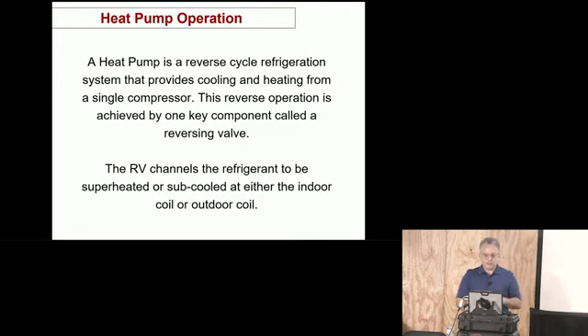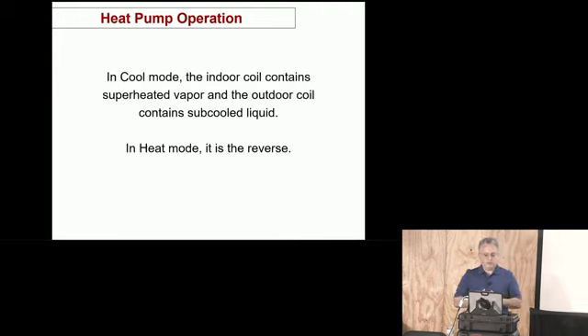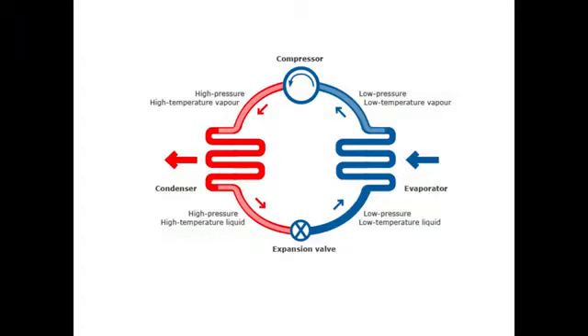Most of us understand that. In cool mode, the indoor unit contains superheated vapor, and the outdoor unit contains subcooled liquid. In heat mode, it's the reverse. And so here's an illustration of a very typical refrigeration system. This is not a heat pump. This is just a refrigeration system.